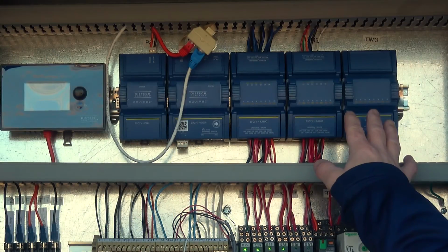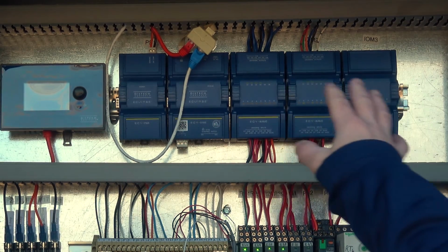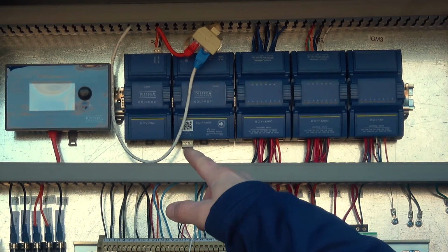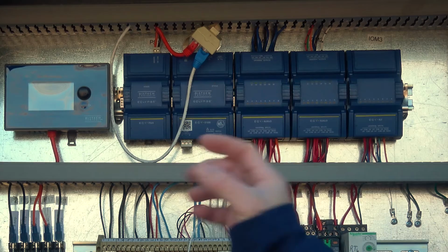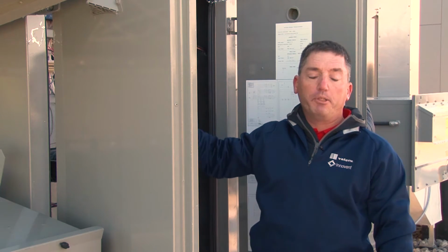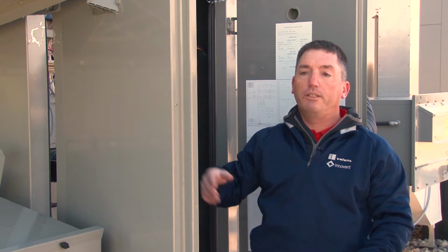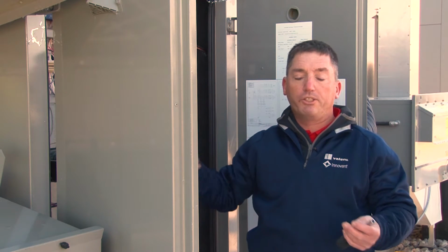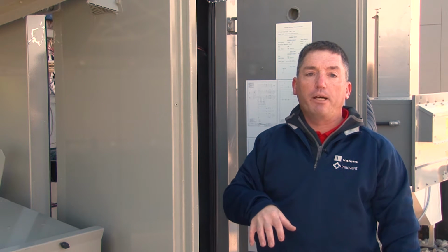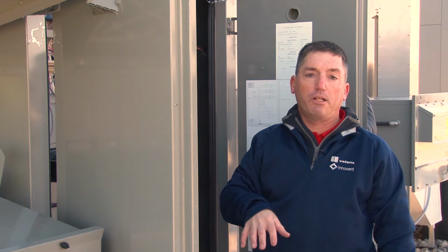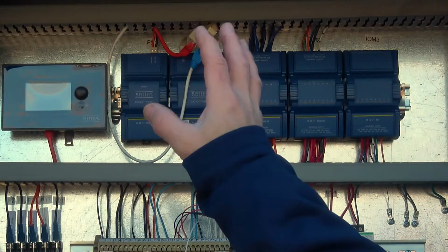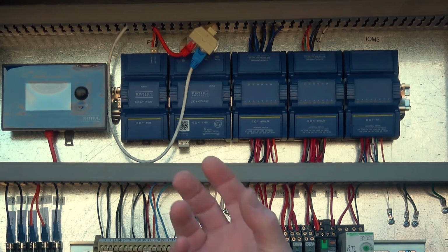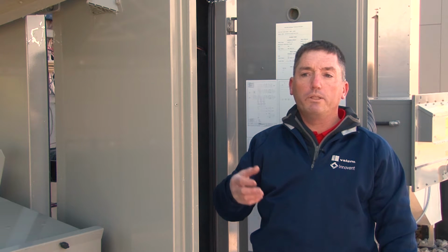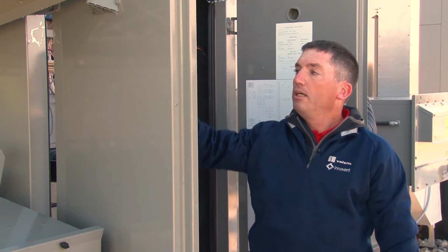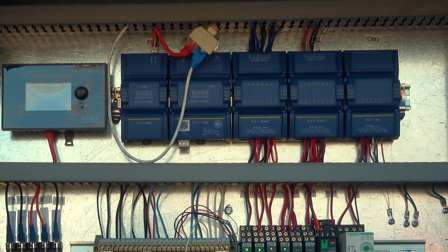At the top of the electrical section on all 4 units, you'll see the blue Distech PLC assembly. Each one has what we call a local HMI, which basically is a local interface where if you come up to the unit and you want to do some troubleshooting, or you want to check the status of the unit, you can go into that screen and see what the various commands are, if there's any alarms present, and what the current status of the unit is. The 4 operator keypads that are downstairs in the maintenance closet basically repeat information from this unit, but only the information that the end user would need to adjust on a day-to-day basis.